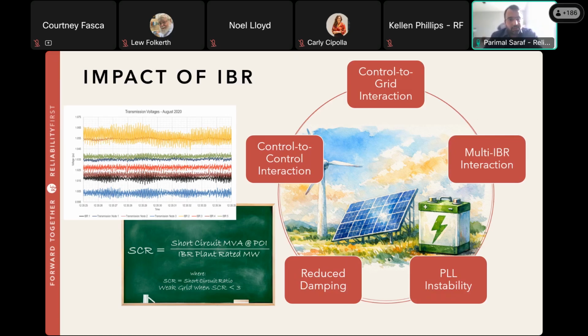And then another phenomenon is multi-IBR interaction, where different IBR plants that are in close vicinity to each other interact, and that essentially triggers oscillations into the grid. And this has been observed predominantly under weak grid conditions where the grid strength is low. A good example of this type of phenomenon is what has been seen in the Panhandle area of Texas, which is predominantly IBR generation. It's a weaker portion of the Texas interconnection, and multiple IBRs that are closely installed to each other exhibit interactions and have been shown to inject oscillations into the system. So that's another phenomenon that has been noticed in weaker portions of the electric grid.